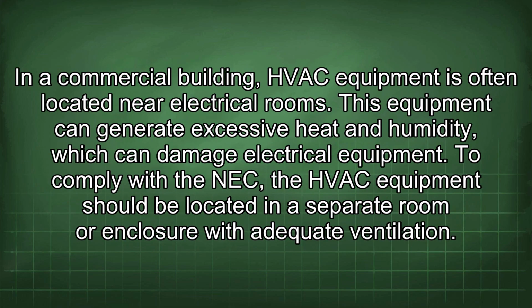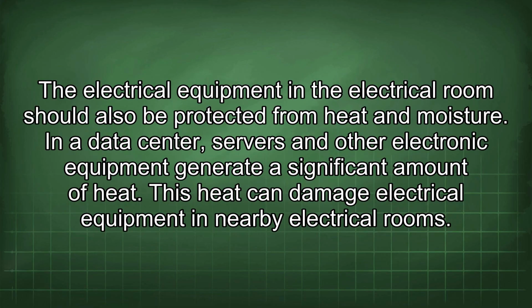In a commercial building, HVAC equipment is often located near electrical rooms. This equipment can generate excessive heat and humidity, which can damage electrical equipment. To comply with the NEC, the HVAC equipment should be located in a separate room or enclosure with adequate ventilation. The electrical equipment in the electrical room should also be protected from heat and moisture.